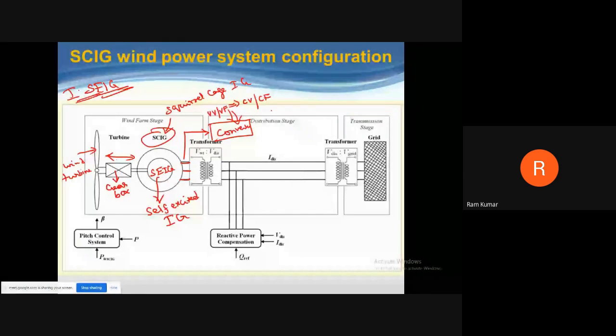When it is constant voltage and constant frequency, we give it to the transformer, where it is stepped up and given to the distribution stage. Then at the grid side, the transformer is there. Depending upon the grid voltage, whether it may be 32 kilovolt, 110 kilovolt, 132 kilovolt, 230 kilovolt, 440 kilovolt or 660 kilovolt, whatever the case, we have to step up or step down.